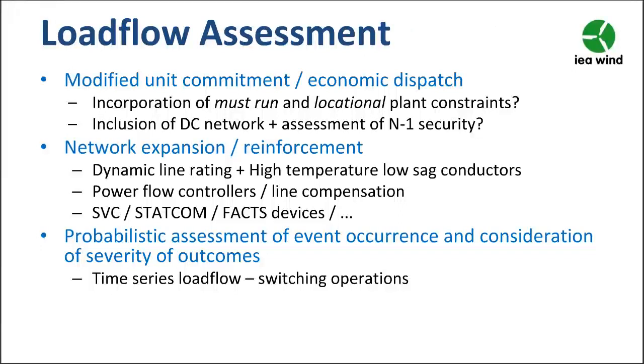Because we're looking at a future scenario, we shouldn't restrict ourselves to the present day system. So we might want to think about whether there are advantages to including things such as dynamic line rating or new high temperature low sag conductors. We could try to make use of SVCs, STATCOMs, and so on. But in the back of our mind, we're thinking about the likelihood of event occurrence, and hence whether it's worthwhile investing large sums of money or time in actually solving these problems.